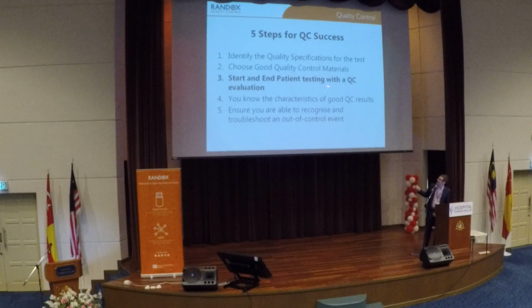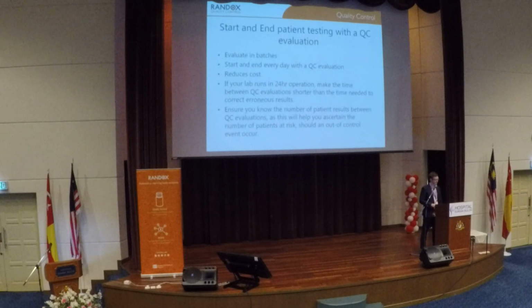is to start and end patient testing with a QC evaluation. So we should evaluate in batches. What does that then mean? Our QC procedure should directly reflect how many patient samples we are running per day. So again, it would make sense maybe to run QC after every 50, after every 100 patient samples, something like that. We should start and end every day with a QC evaluation. Ultimately, that is going to save us money in the long run.